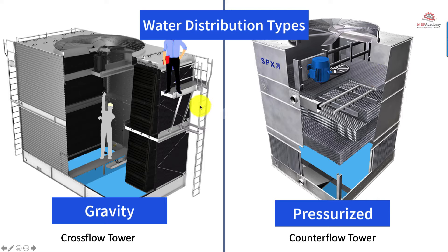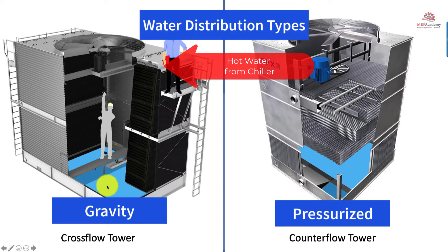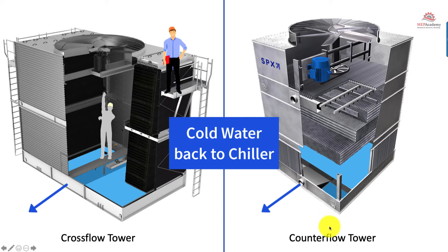In the cross flow, the hot water dumps into the hot water basin at the top, which has little holes in it, and the water trickles out by gravity through the fill into the cold water basin. Both tower types have a cold water basin, from which the cooled water is returned to the chiller to pick up the heat from the water-cooled chiller.